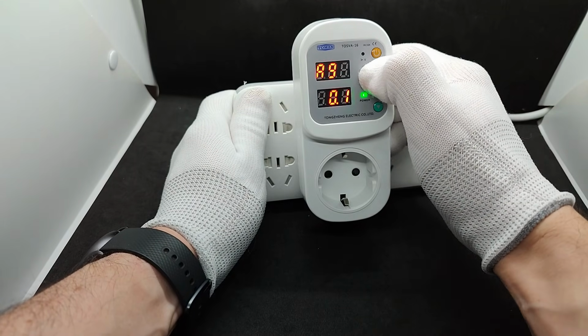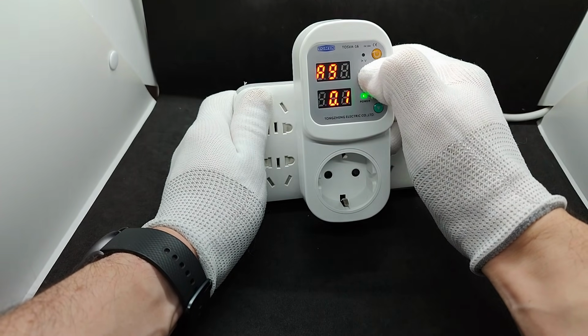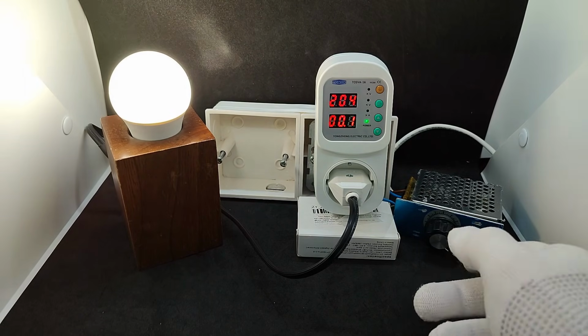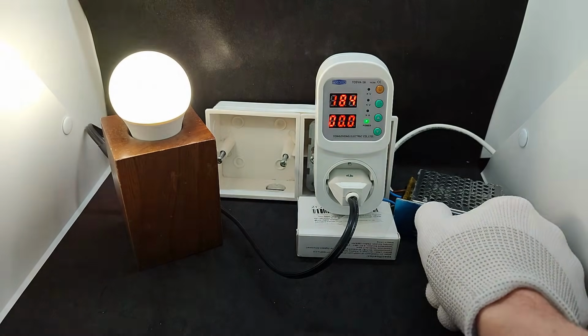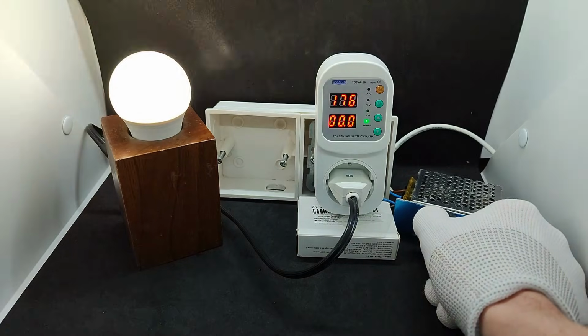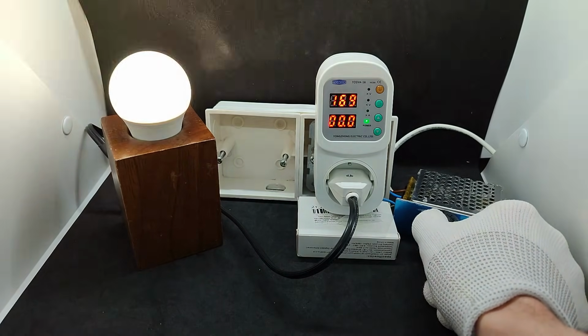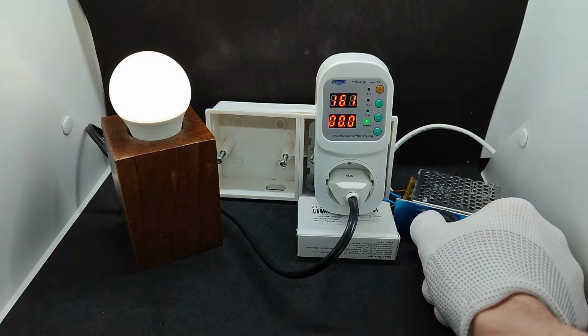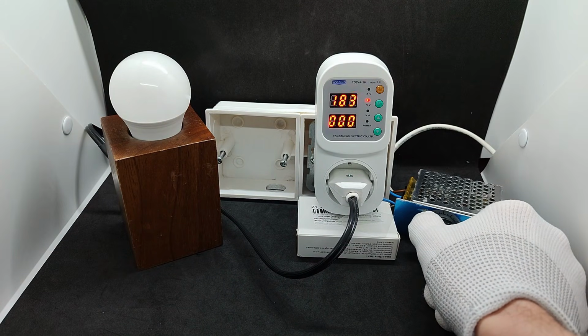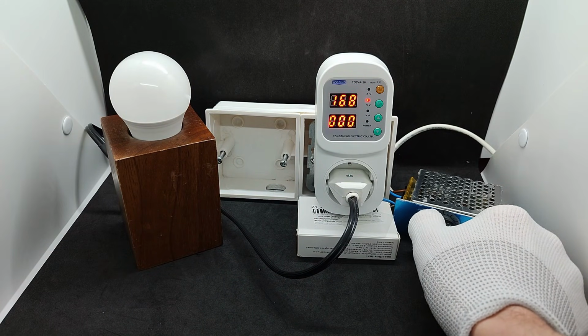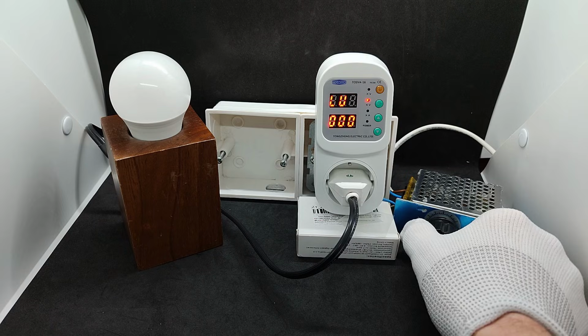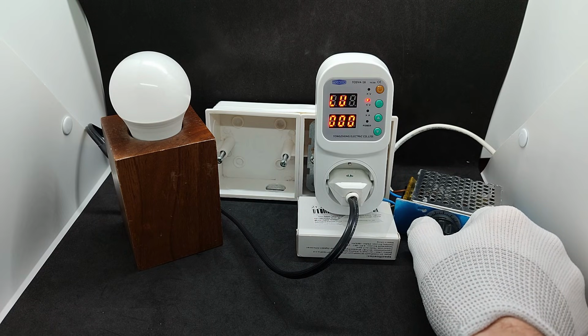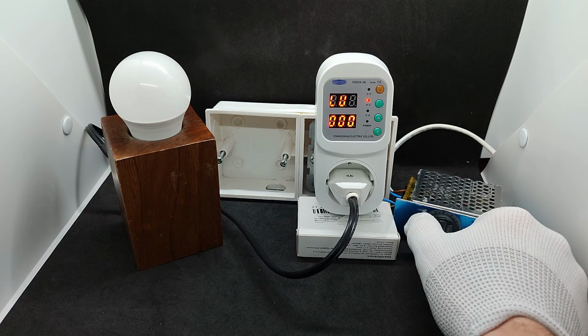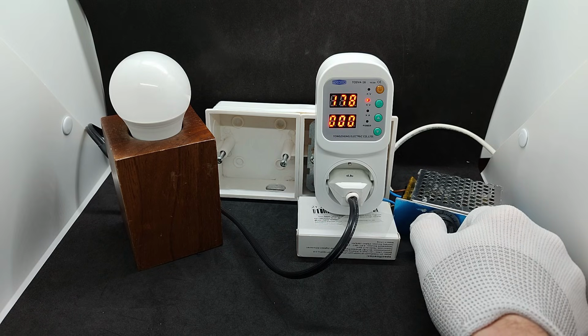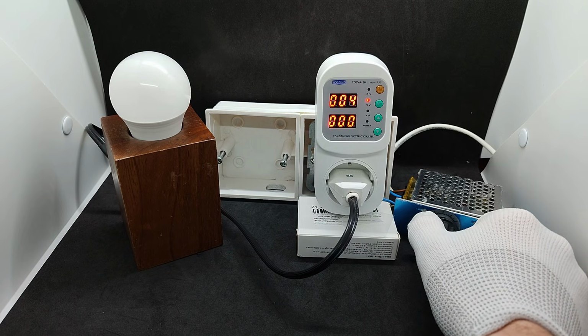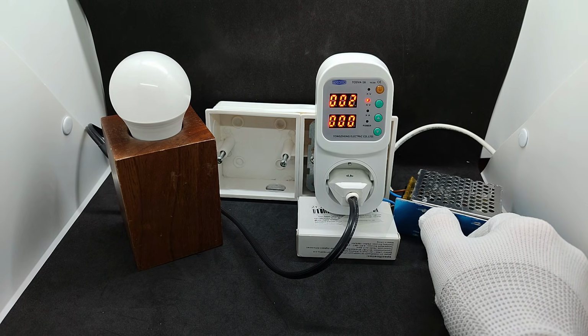By holding the set button, I exit the menu. For the test, I connected the relay through a dimmer. We lower the voltage. Until the set threshold of 160 volts is reached, it will remain on. When it is reached, it will turn off almost instantly, with a delay of 0.1 seconds. The corresponding LED lights up on the panel, and it will remain off until the voltage reaches the turn-on threshold of 180 volts. After that, a 5-second delay starts and the relay turns on.